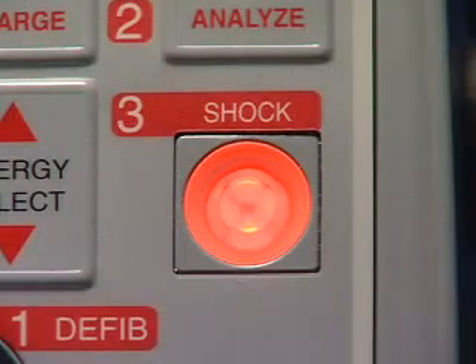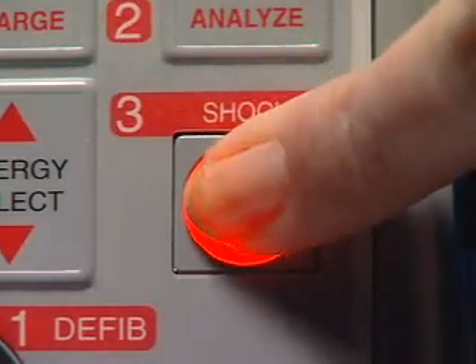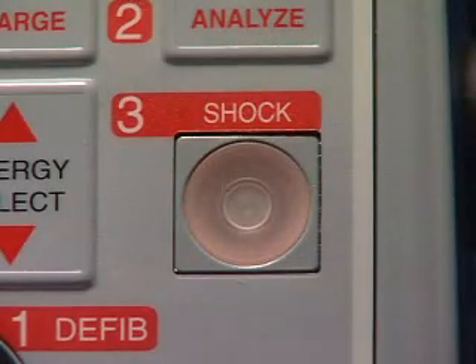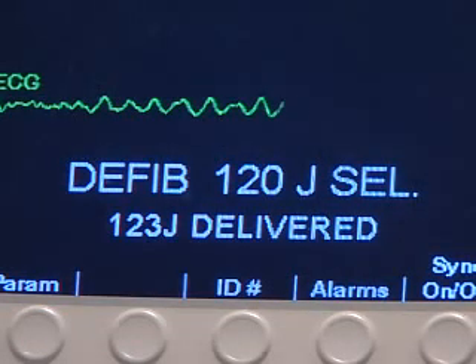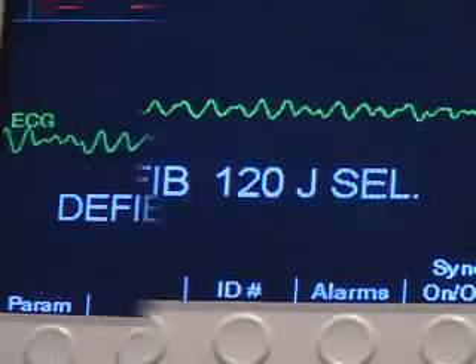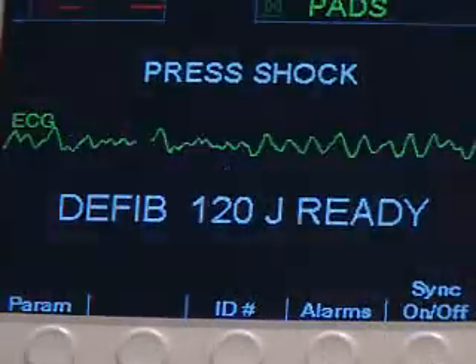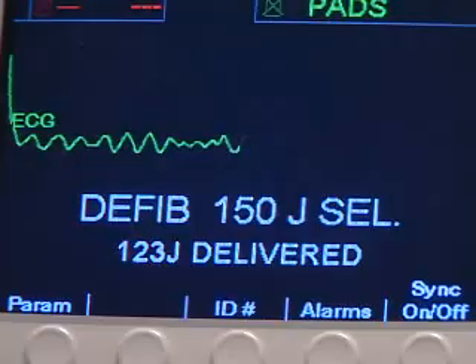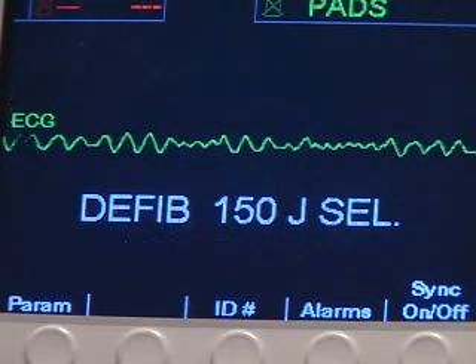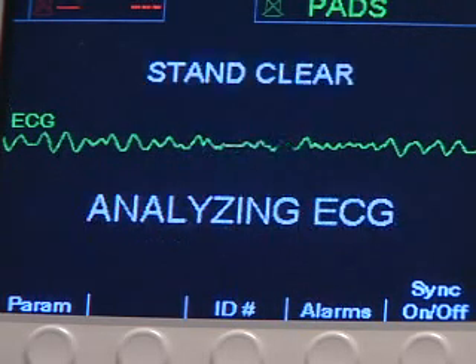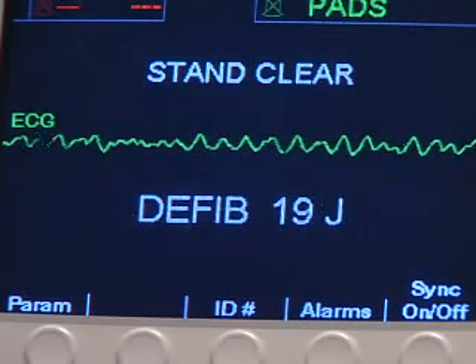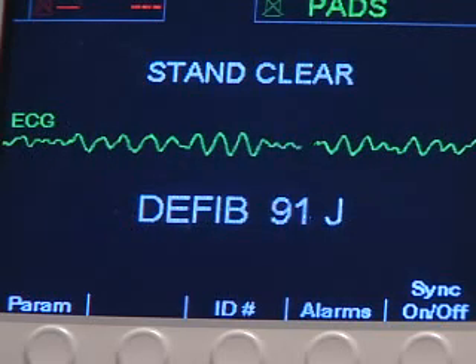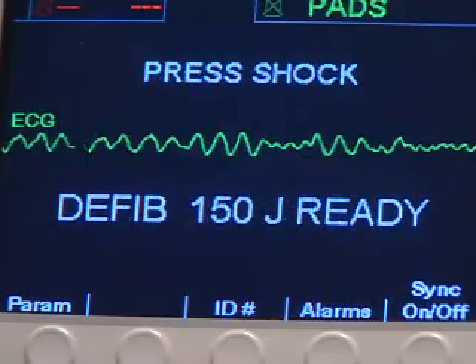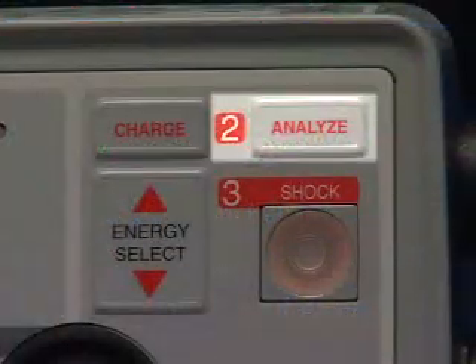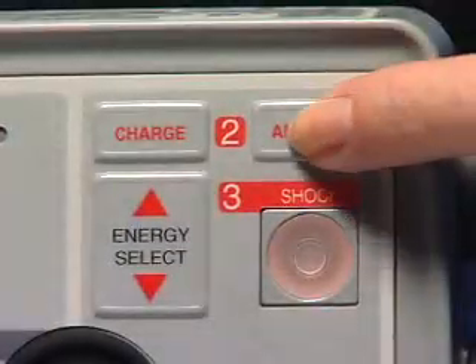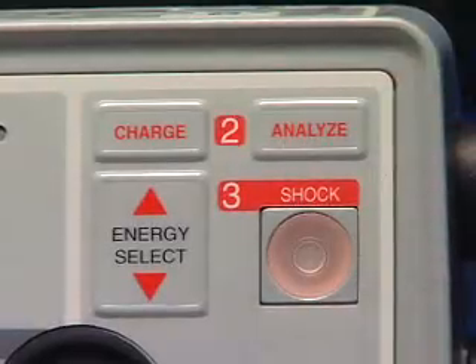Press and hold the shock button on the front panel until the energy is delivered to the patient. Observe the patient and the ECG response to make certain the shock has been delivered. After the shock has been delivered, and depending on the configuration, the E-Series display will either return to the energy selected or will escalate to the next energy setting. Press the Analyze button to restart the ECG analysis and to determine if additional shocks are required.